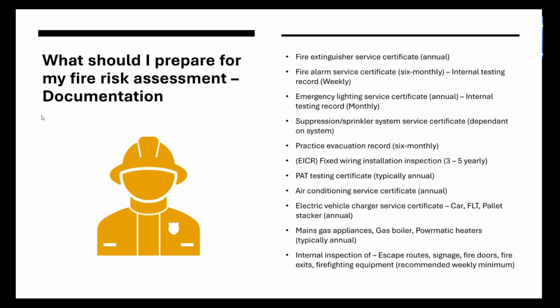We have our certificate available. And also, quite often when I go to do a fire risk assessment, I will look around the actual outlet area of the air conditioner, especially if it's in the ceiling, for dust and build-up of dirt around the outside of it. If we have that, it should be cleaned, as it can blow hazardous things into the environment, hazardous dusts and other chemicals.